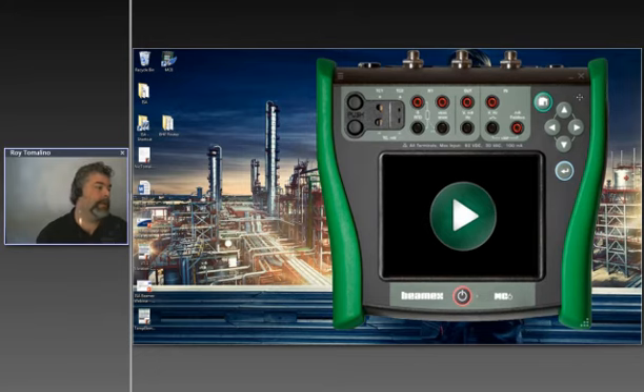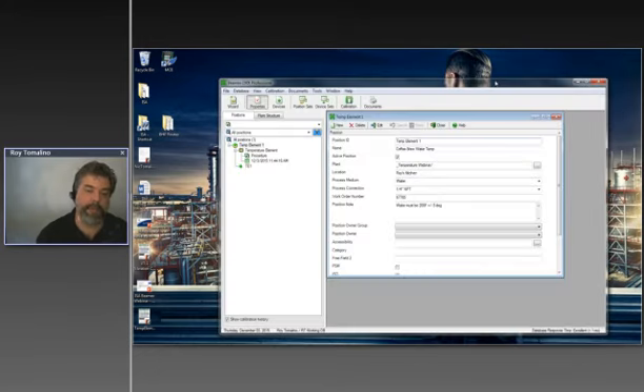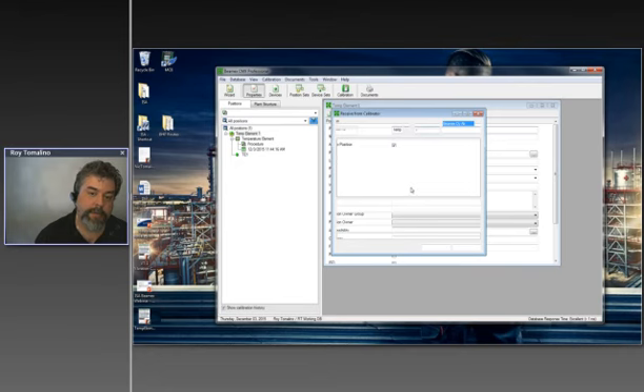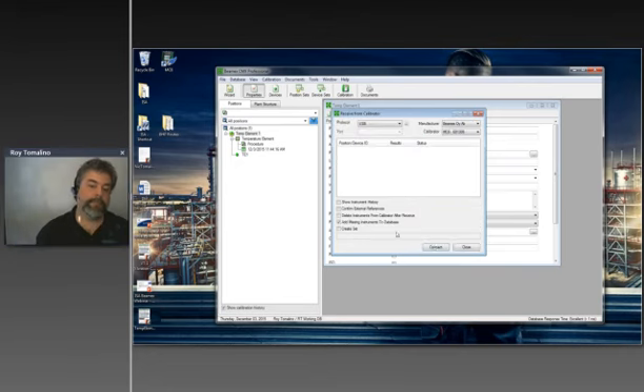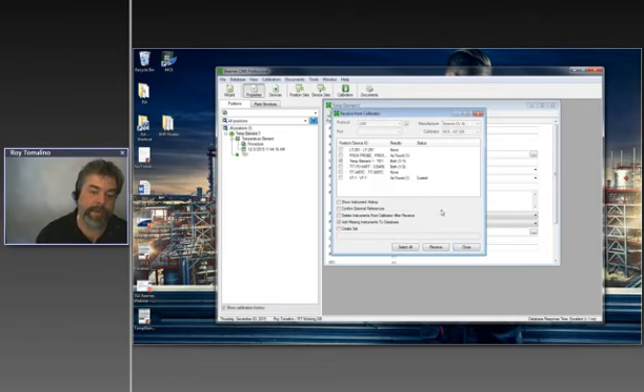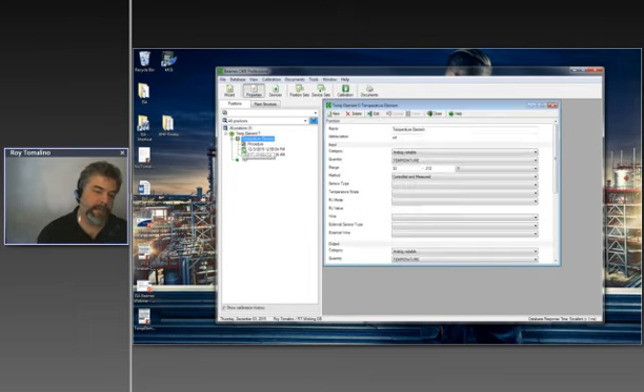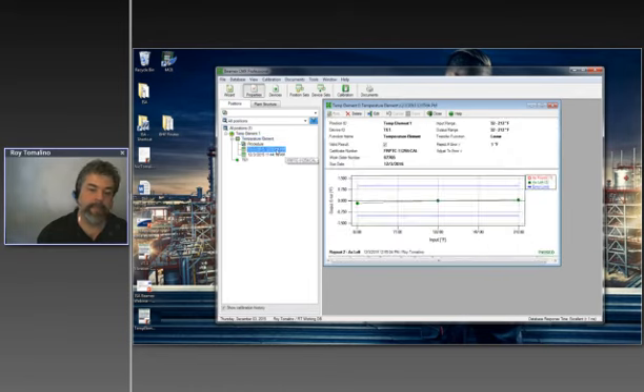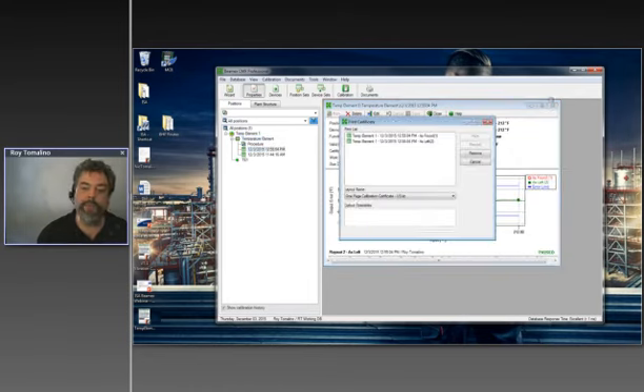So let me disconnect my calibrator. I'll bring over my software and just unload this real quick. This is called temp element 1. Let me receive that. So I'm bringing over those test results, and if I wanted to see them electronically, this is it. I'll right click and we'll show you a preview of the calibration certificate itself.